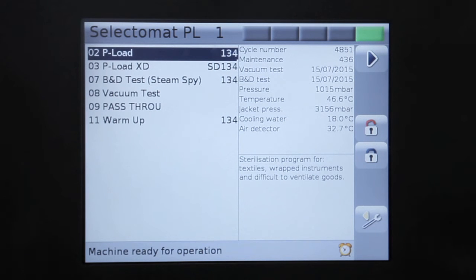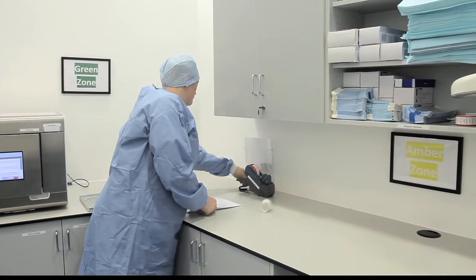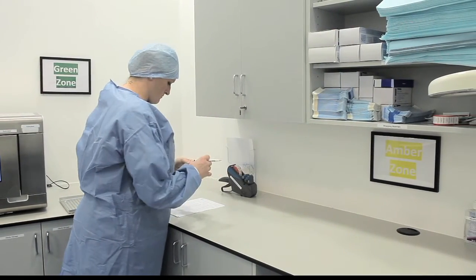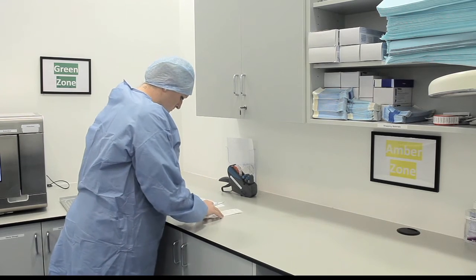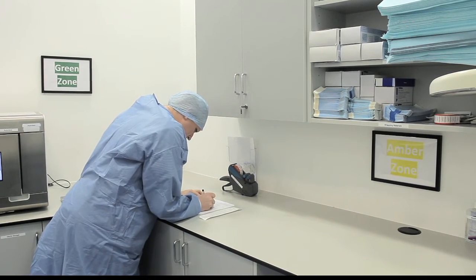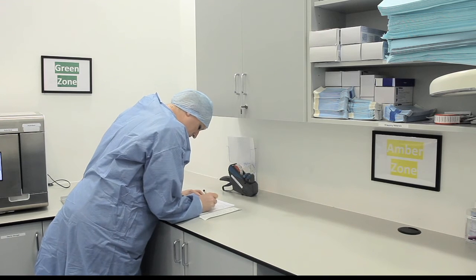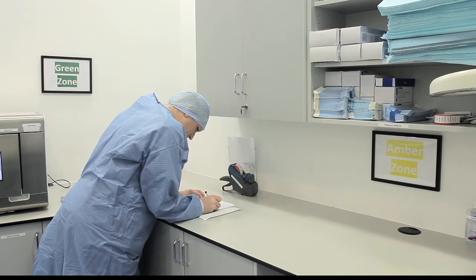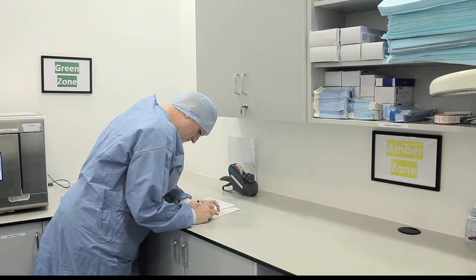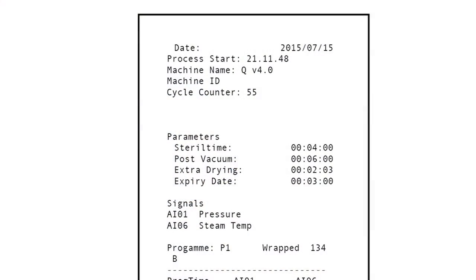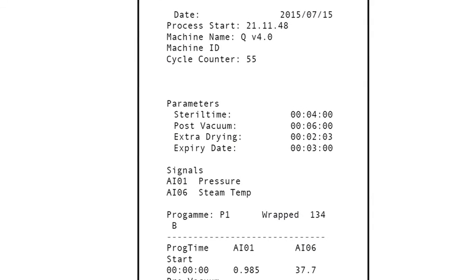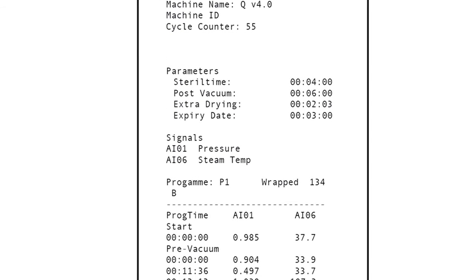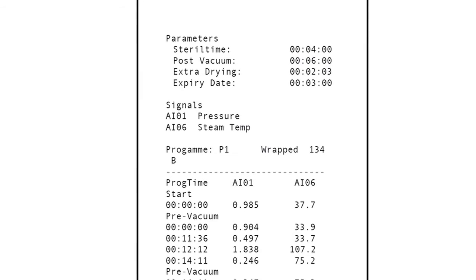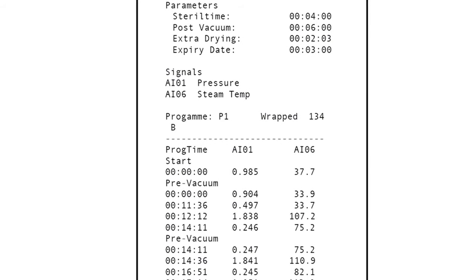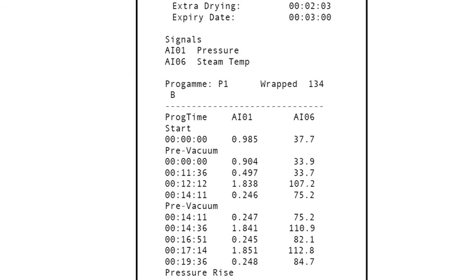The dental healthcare worker now checks the graph. This is carried out after each cycle is completed in the autoclave. The graph printout is designed to show that the operating cycles are functioning correctly, and therefore sterilisation has been achieved. The graph printout will give a reading of the sterilisation parameters that the autoclave has reached during the cycle. It is critical to ensure that this section of the graph is analysed correctly. The key parameters to be checked are date, cycle number, temperature, and holding time.